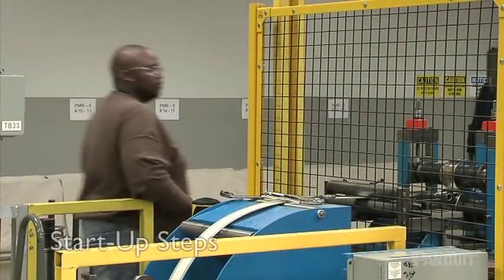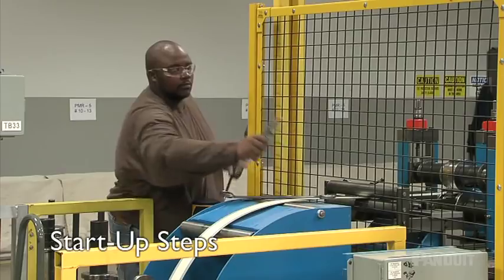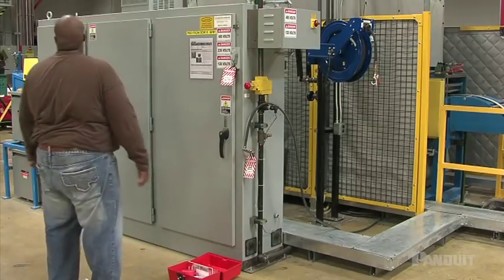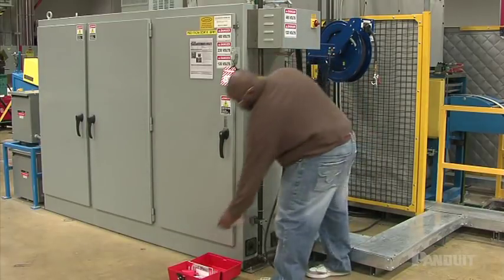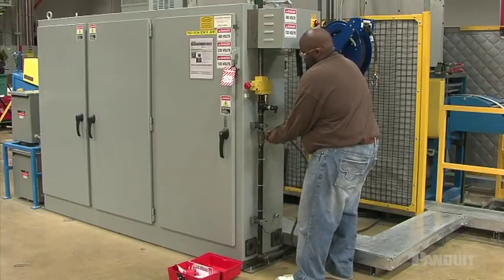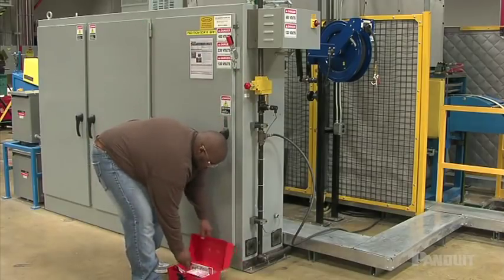Startup is every bit as important as shutdown. When the work is completed, follow procedures for restoring the equipment to running conditions. First, make sure you remove all tools, reconnect any lines, and put machine guards back in place. Before you remove the lock and tag and re-energize the equipment, announce that the equipment is being turned on again and confirm that all employees are safely positioned. Lockout-tagout devices can now be removed by the employee who applied them. If you are the last one to unlock, notify the area supervisor before restoring energy. When all locks and tags are removed, restore energy to the equipment. Finally, ask the responsible operator to test run the equipment to make sure it's operating correctly before you leave.